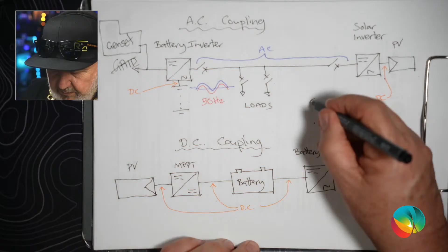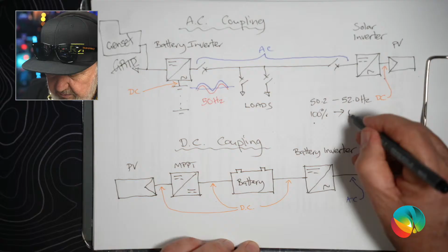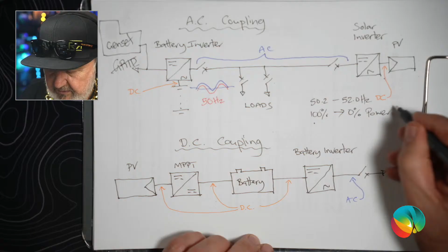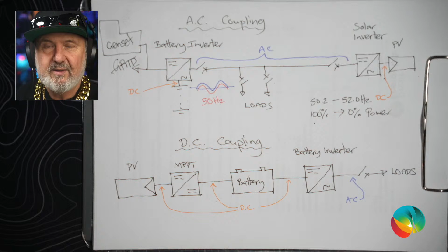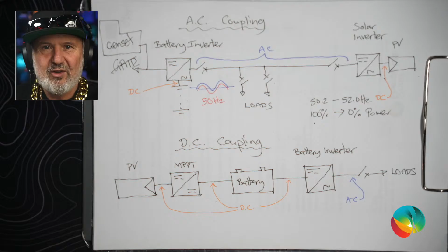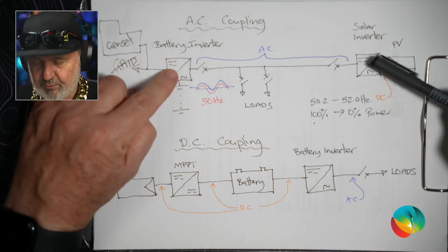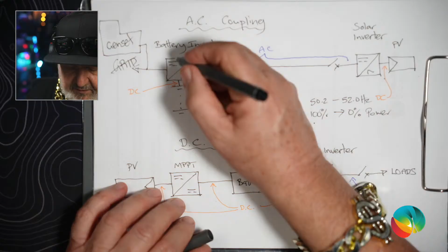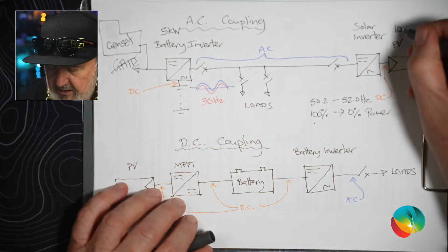The default values are from 50.2 hertz up to 52.0 hertz, which is the range where you go from 100% power down to 0% power. So that's a way of controlling the amount of generation with a small amount of frequency change. It's pretty clever. I think it was pioneered by SMA actually over 20 years ago, but it's been adopted because the standards refer to it. Many inverters do this anyway, but it's still not perfect because you're going to have to consider the ratio of these two. For instance, let's say this is a 5 kilowatt inverter, but we've got 10 kilowatts of AC power over here.